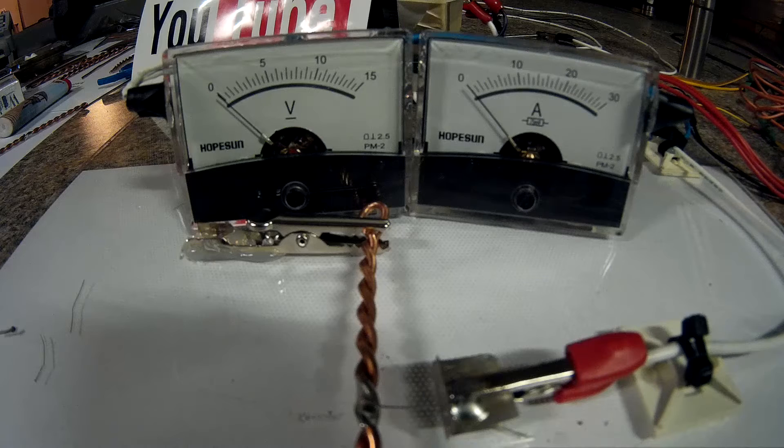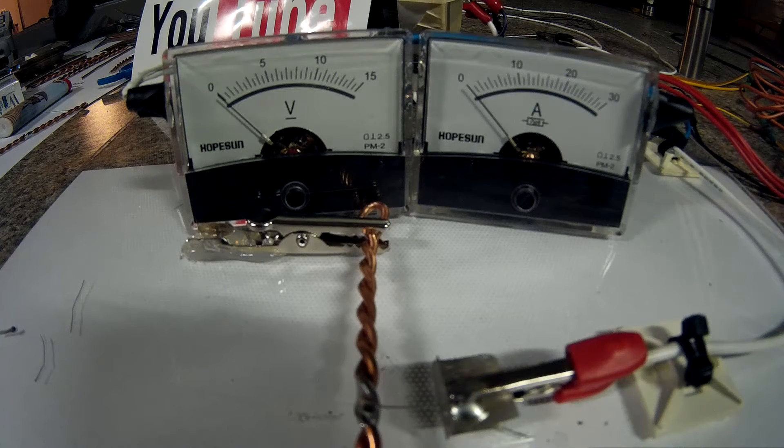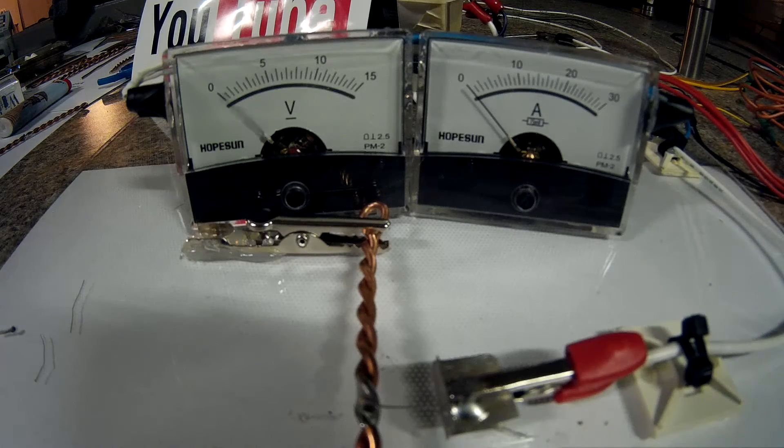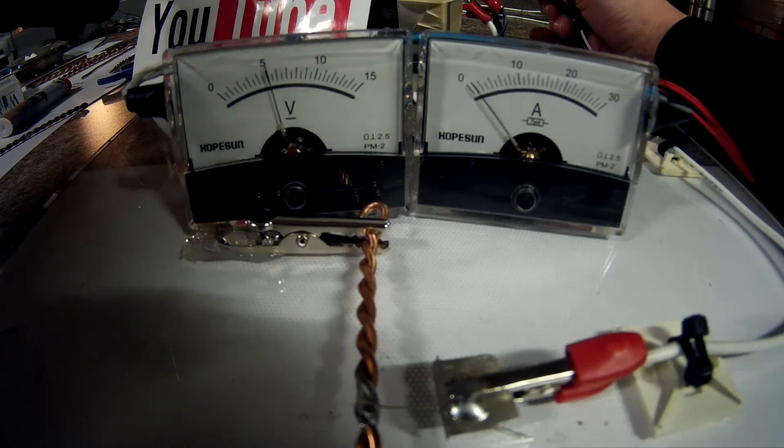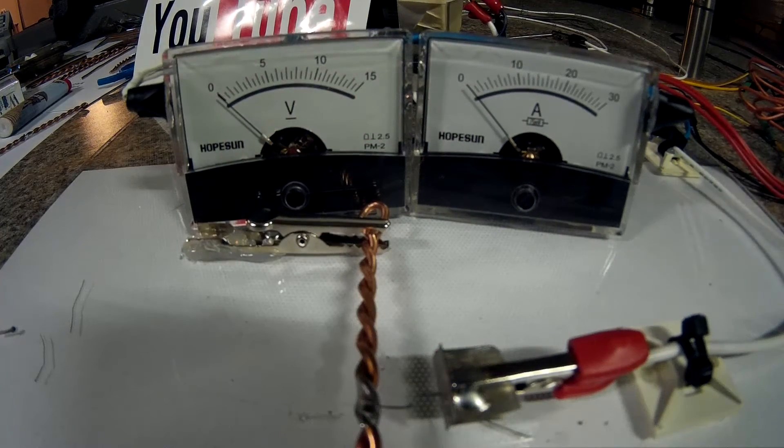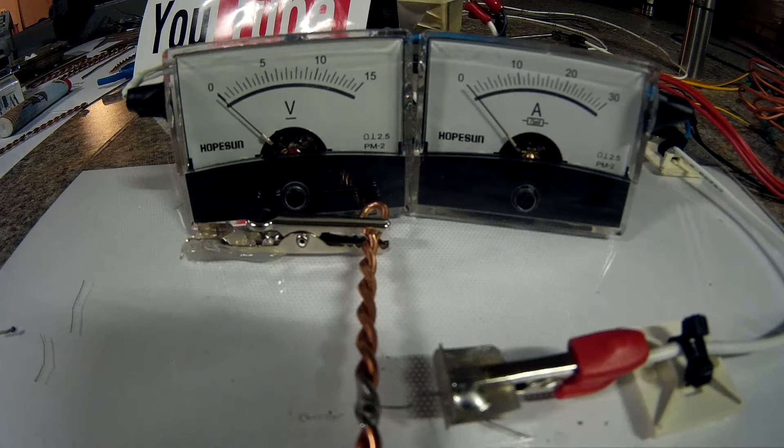Okay, that previous wire was the 14 gauge. This next one is the 12 gauge and the gap is set at 9.93 millimeters. Contact. Okay, that just got up to 10 amps and then popped.